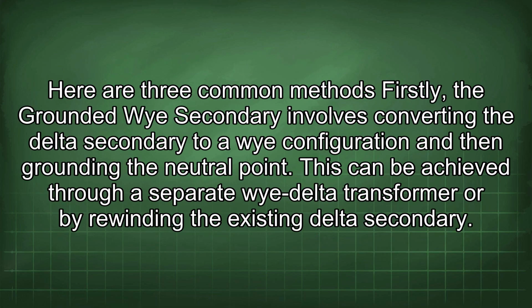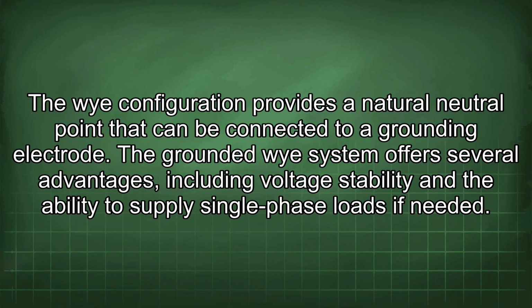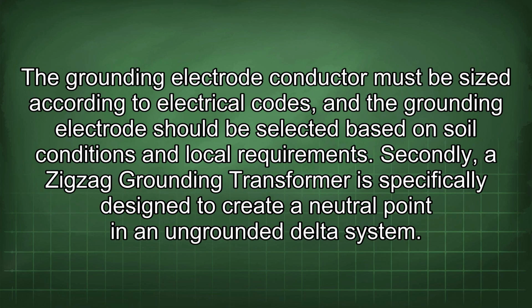Here are three common methods. Firstly, the grounded Y secondary involves converting the delta secondary to a Y configuration and then grounding the neutral point. This can be achieved through a separate Y-delta transformer or by rewinding the existing delta secondary. The Y configuration provides a natural neutral point that can be connected to a grounding electrode. The grounded Y system offers several advantages, including voltage stability and the ability to supply single-phase loads if needed. The grounding electrode conductor must be sized according to electrical codes, and the grounding electrode should be selected based on soil conditions and local requirements.